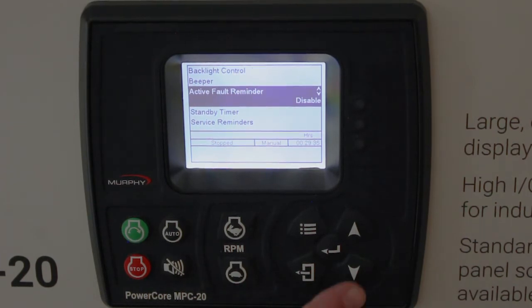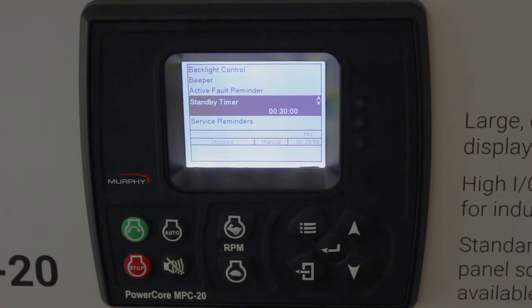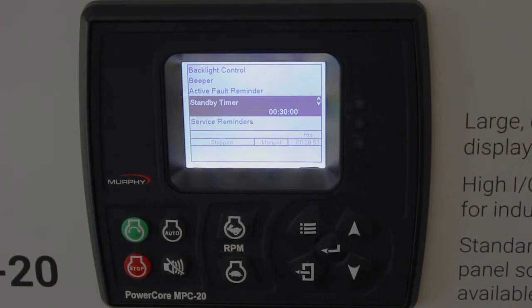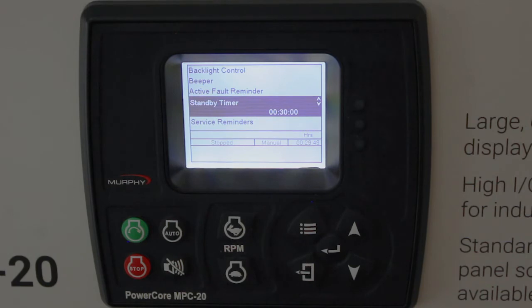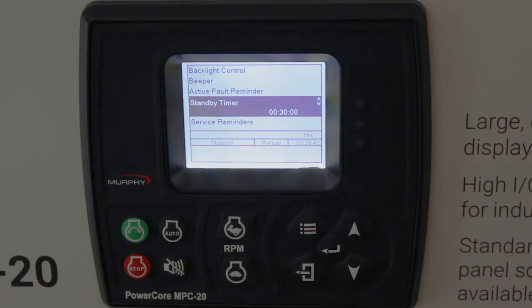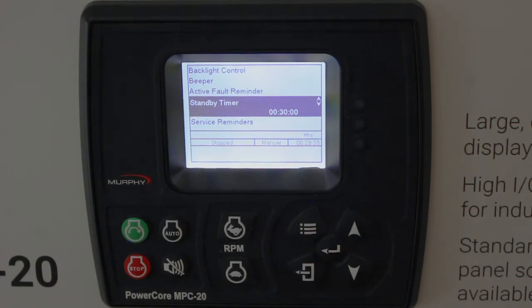The standby timer defaults to 30 minutes. It can be set to anytime you want. If a button isn't pushed or a start signal is not received for 30 minutes, the backlight and the heater turn off and it saves battery consumption. By hitting any button, or if a start signal occurs when you're in auto, it leaves standby and goes back to normal operation.